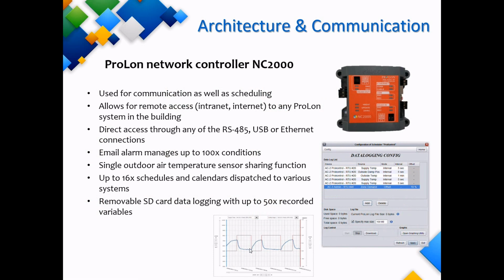Okay, on to our last controller, the NC2000 network controller. As I mentioned before, this device is necessary for any kind of remote connection. It can also act as a central scheduling device. We can configure up to 16 separate schedules and redistribute them to any controller on the network. This makes it easier for any kind of schedule change. Instead of changing it in each individual device, we can centralize it through the network controller.